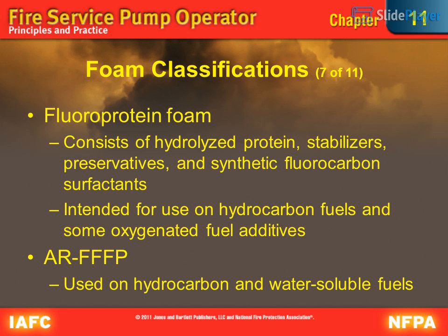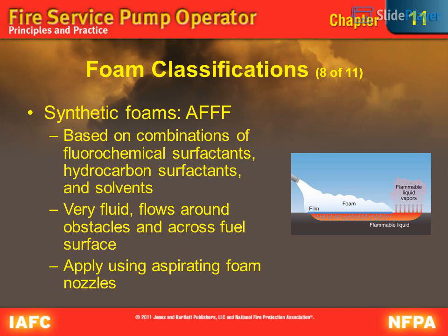AR-FFFP. Used on hydrocarbon and water-soluble fuels. Foam classifications, 8 of 11. Synthetic foams, AFFF. Based on combinations of fluorochemical surfactants, hydrocarbon surfactants, and solvents. Very fluid, flows around obstacles and across fuel surface. Apply using aspirating foam nozzles.